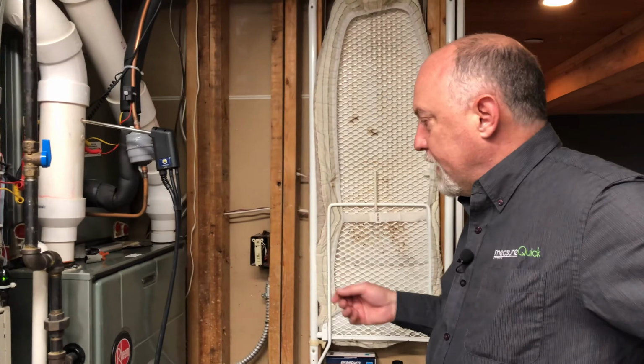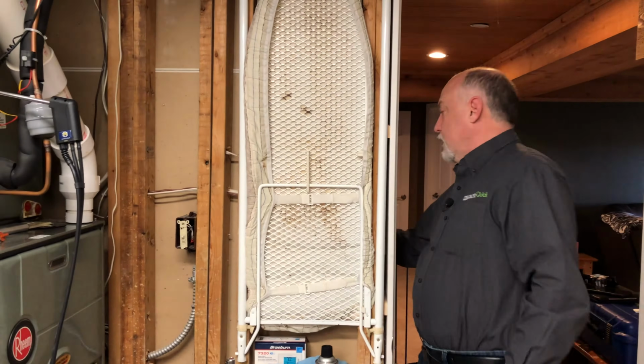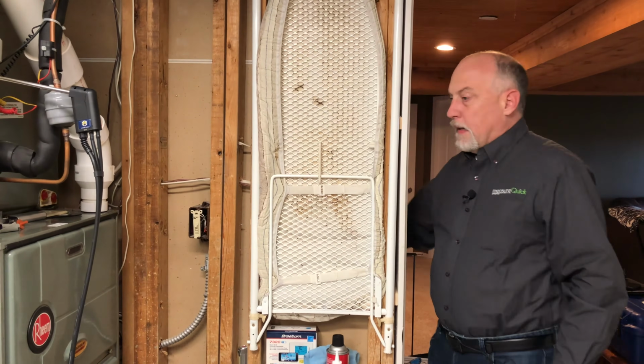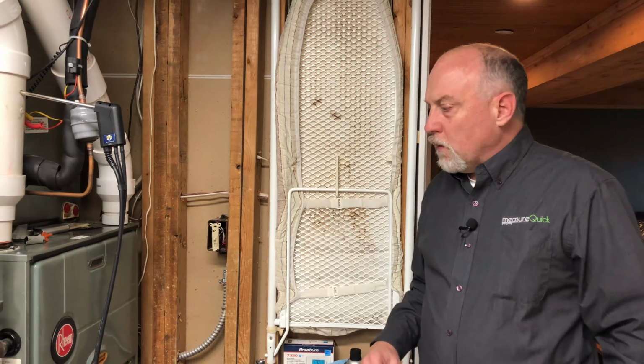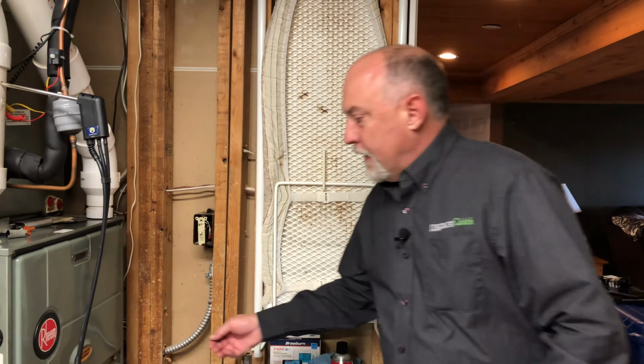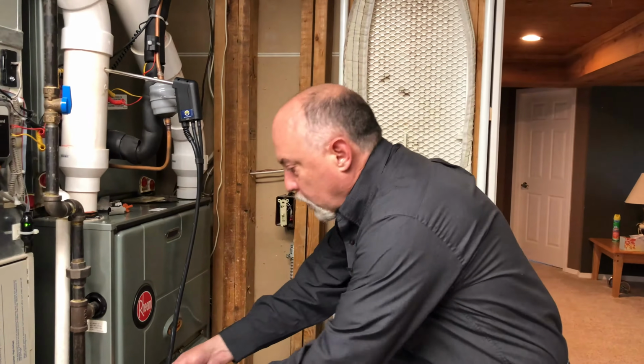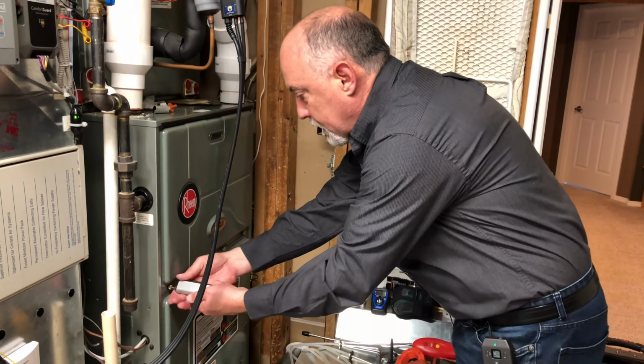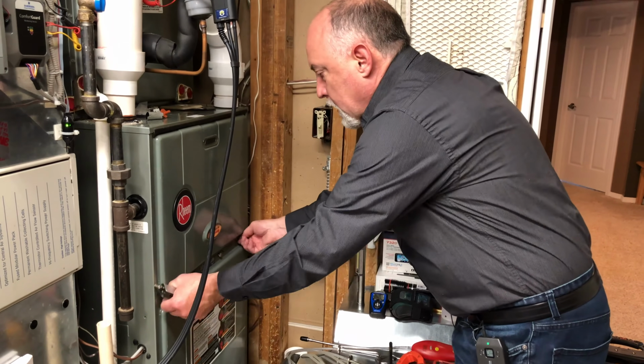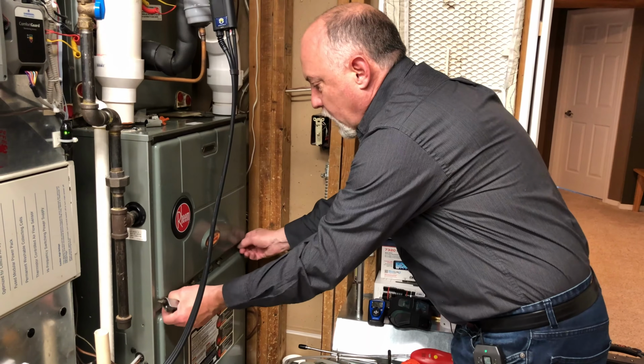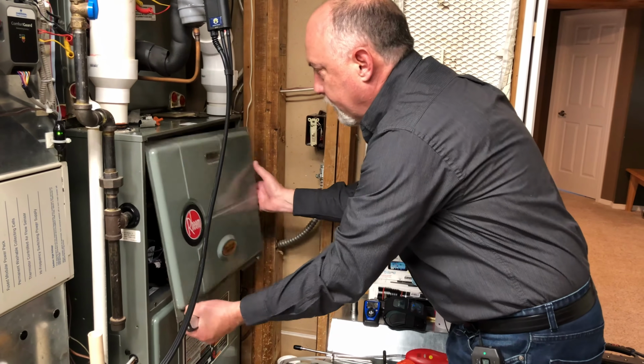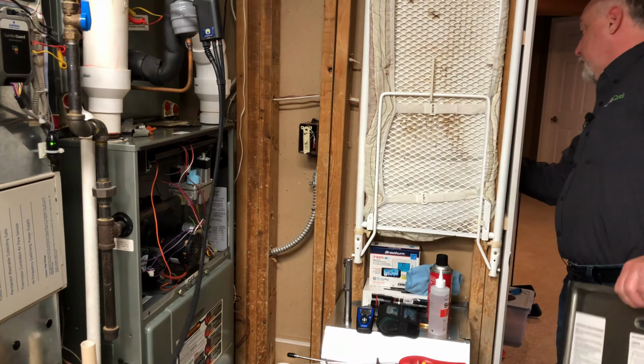So now that we got that set up here, I'm going to go ahead and turn the call back down, and we're going to end the call for heat here, and then I'm going to go ahead and start taking some things apart, and we'll do an inspection. You want to let the furnace cool down naturally. You just don't want to kill the switch, because I might have to turn it down a little bit further here.